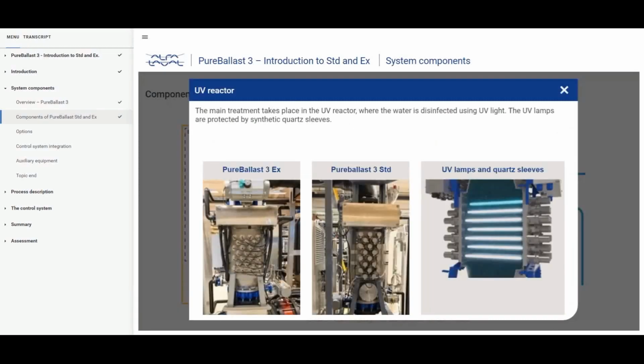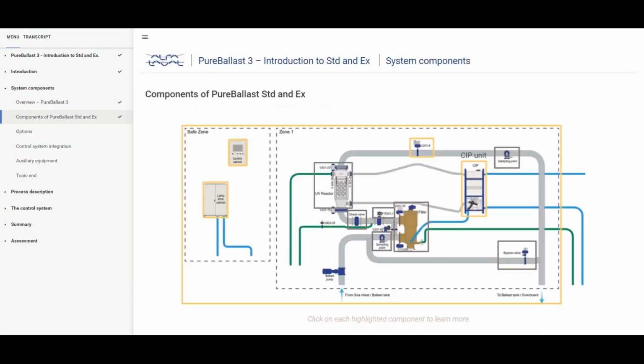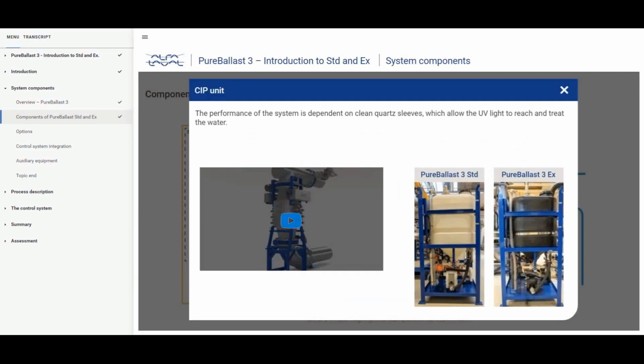The main treatment takes place in the UV reactor, where the water is disinfected using UV light. The UV lamps are protected by synthetic quartz sleeves. To save power, a UV sensor monitors the need for light in the reactor to avoid using more power than necessary. If the water clarity is low, the power is increased, and vice versa. The performance of the system is dependent on clean quartz sleeves, which allow the UV light to reach and treat the water. The CIP unit circulates a reusable, non-toxic and biodegradable cleaning solution that removes any scaling and dirt buildup that would prevent the UV light from treating the water.